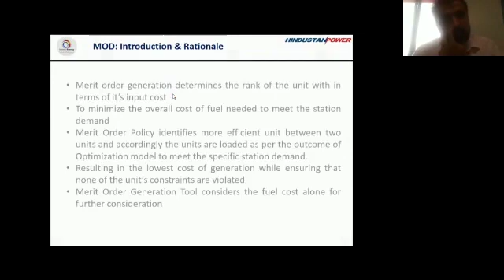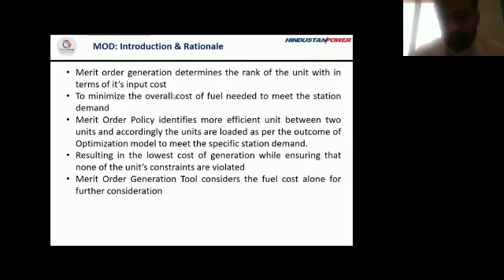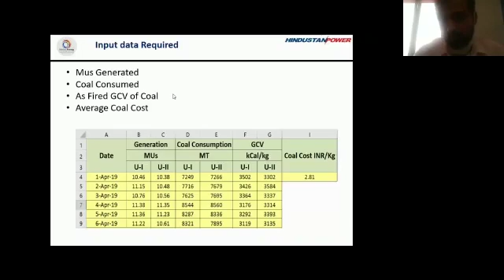Next comes merit order dispatch. This takes into account the fuel cost of the coal for the last historical 365 days at different load conditions. And based on the average GCV that we have received, there are variables which can be used to arrive at a coal cost in terms of rupees per unit. Based on that, I can generate an input to output curve wherein on the y-axis it's cost in rupees per hour, and on the x-axis it is total load on the unit.